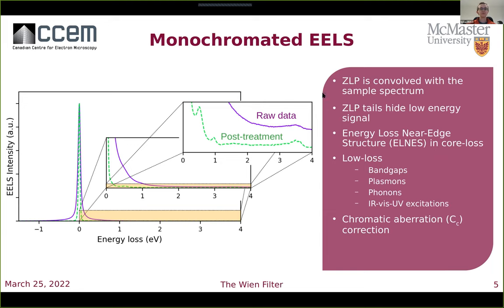The zero loss peak is convolved with the true spectrum from the sample and can result in blurring spectral features together. In the low loss regime, details of the zero loss peak can also hide low energy signals, making them difficult or impossible to identify. Use of a monochromator helps us to reveal, for example in the core loss, the near edge structure, allowing us to identify oxidation or bonding states in different elements.